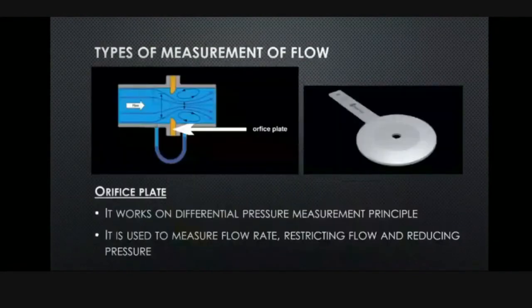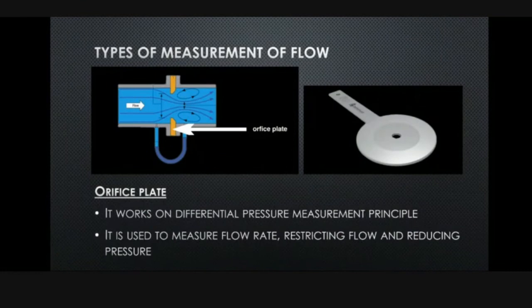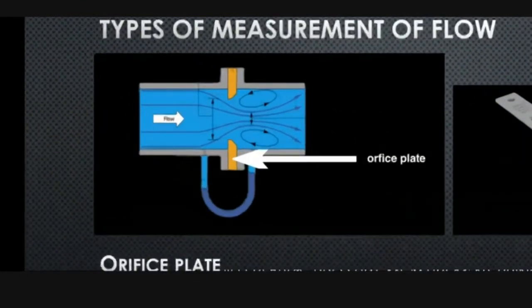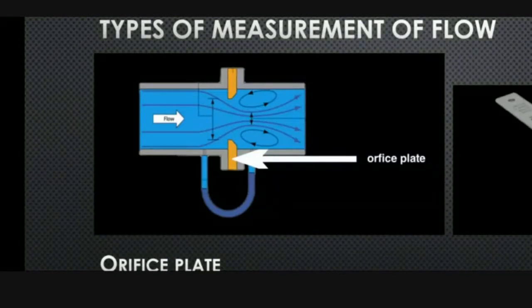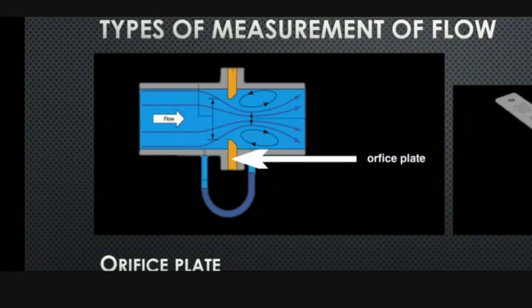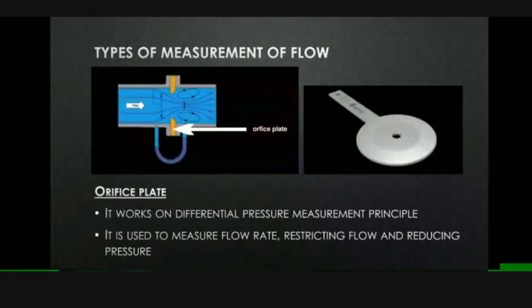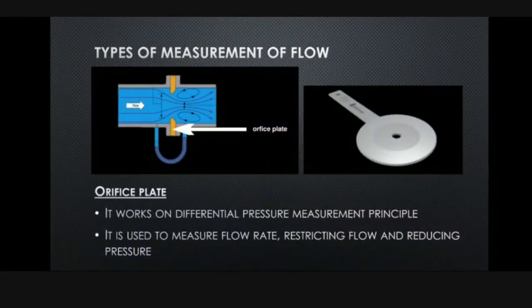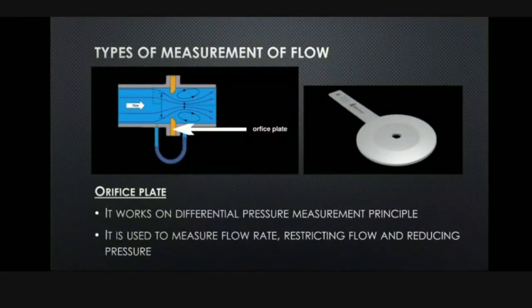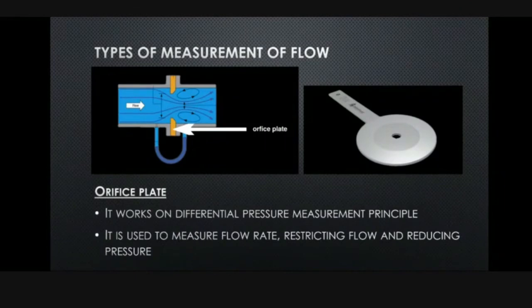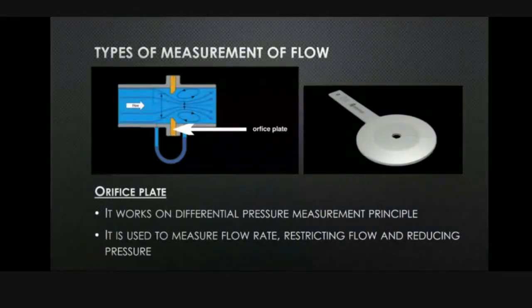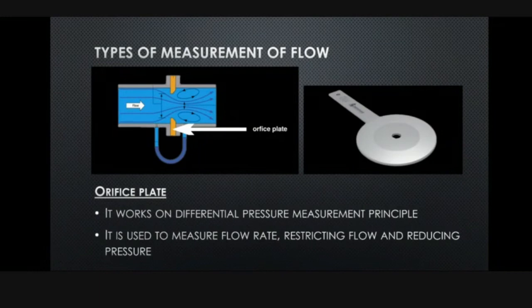We will now discuss the types of flow measurement. First, orifice plate. This is the diagram of it. If we talk about its specification, it starts from 6 millimeter onwards. It's a thin plate, sometimes of stainless steel. It works on the differential pressure measurement principle, and it is used to measure flow rate, restricting flow and reducing pressure. This is the real life image.